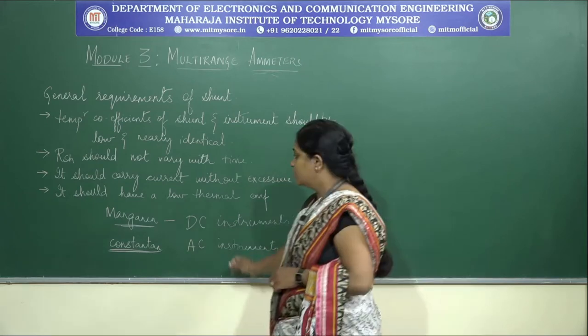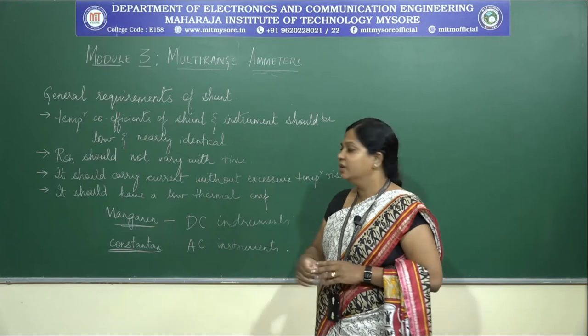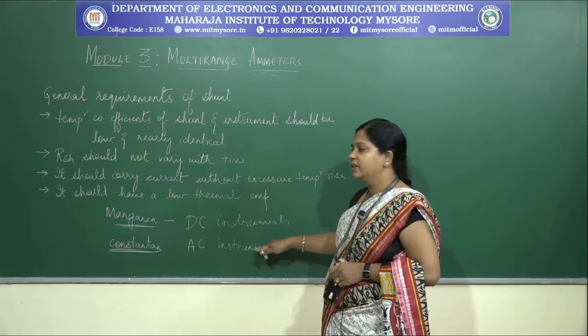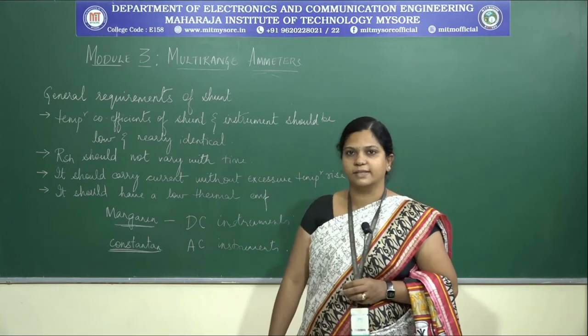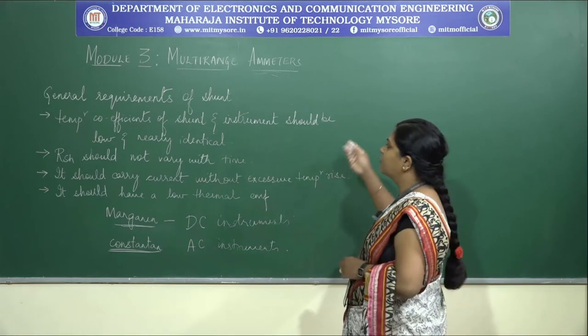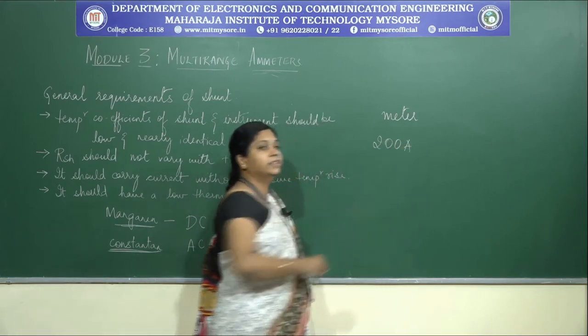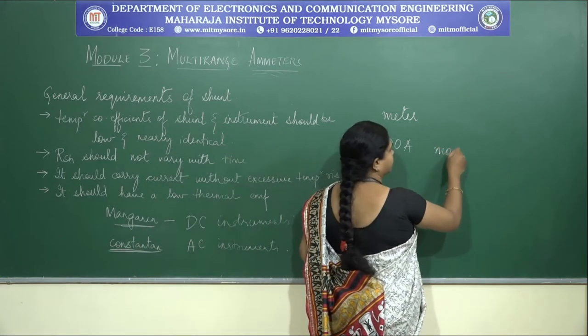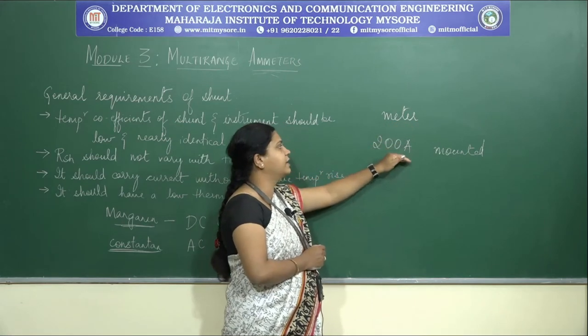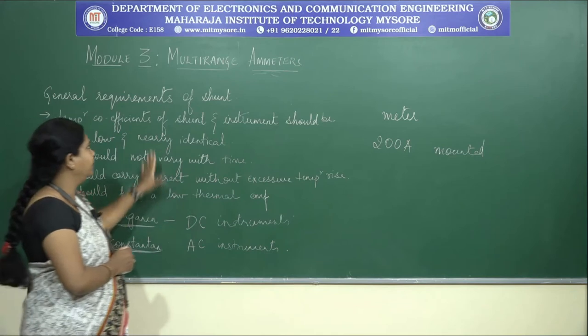Constantan is used as a shunt in AC instruments; it has a higher thermal EMF compared to manganin. Constantan is preferred for AC because manganin's unidirectional effect cannot be used in bidirectional AC circuits. For low currents, the shunt is placed within the meter casing, whereas for currents above 200 amperes, the shunts are separately mounted.